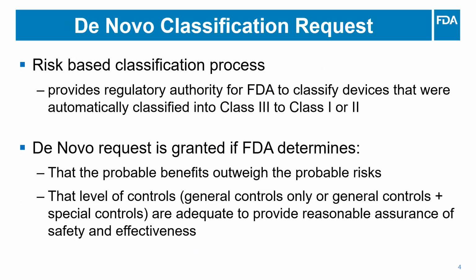However, in 1997, the de novo path was established and enacted to allow novel devices to be classified into Class 1 or Class 2 if general controls, or general and special controls, provide a reasonable assurance of safety and effectiveness when there is no legally marketed predicate device.